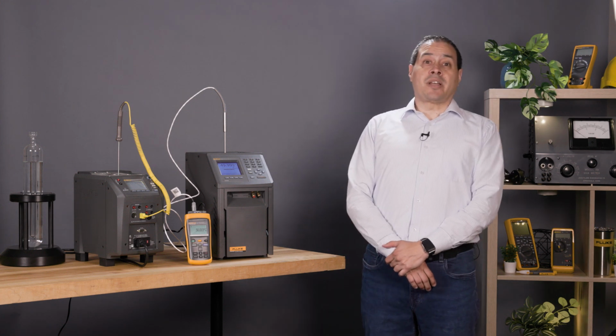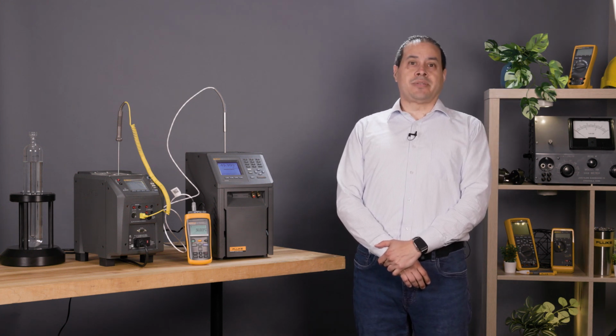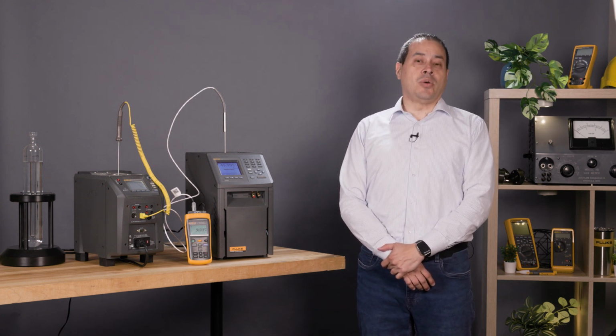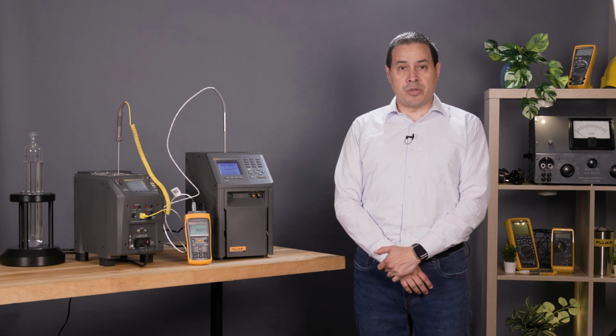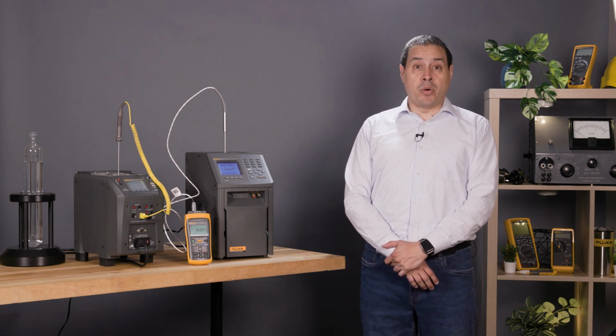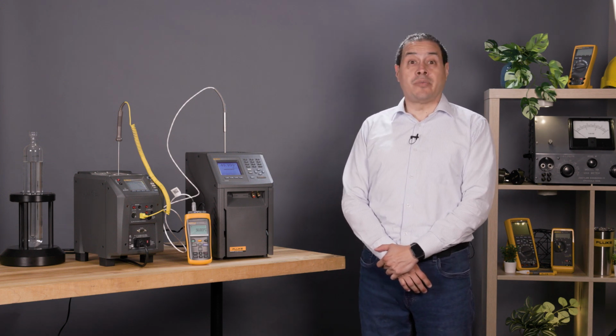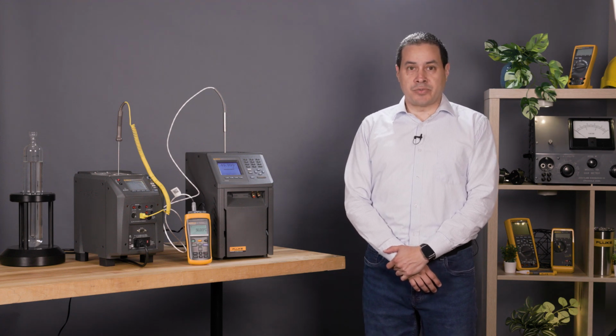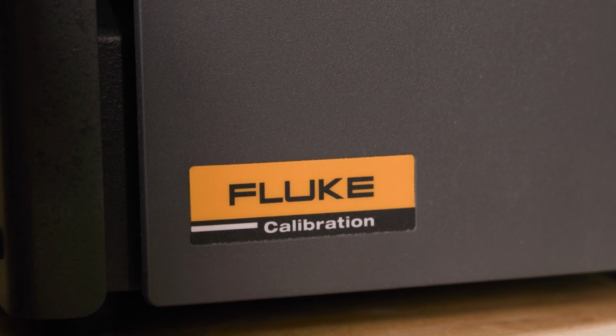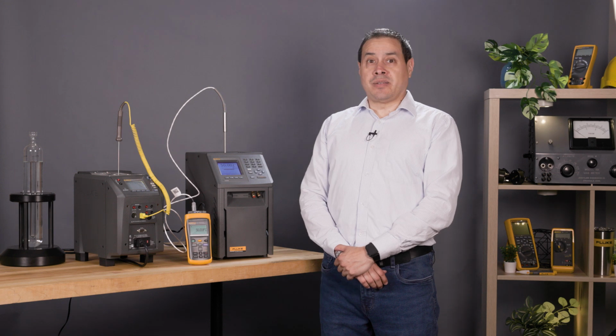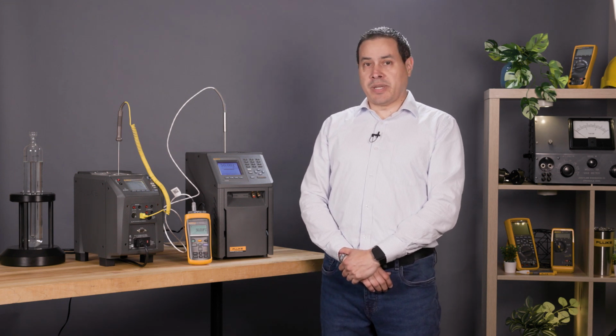Usually you use dry well calibrators because they're faster to reach high ranges. So if you need a low temperature, probably you need a bath. But if you go to 300 Celsius or more, you probably need a dry well calibrator. It will get you faster to your setup. We want to calibrate with a dry well because we want to go to high temperature, so high range. We want to make it faster.